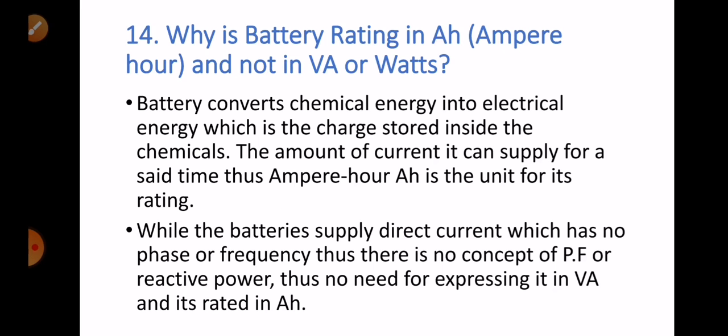Question number fourteen: why is battery rating in ampere-hours, not in kVA or watts? There are two major reasons. First, a battery converts chemical energy into electrical energy — the charge stored in the chemicals determines the amount of current it can supply for a set time, which is why ampere-hour is the unit of battery. Second, batteries supply direct current, which has no phase or frequency. Thus there is no concept of power factor or reactive power, so there is no need to express it in kVA.